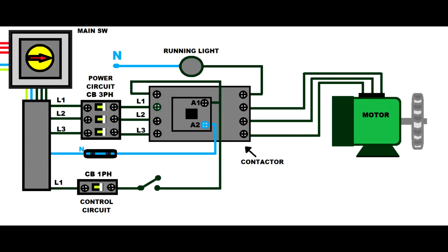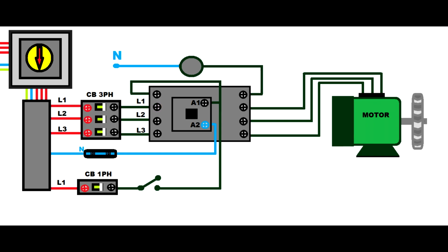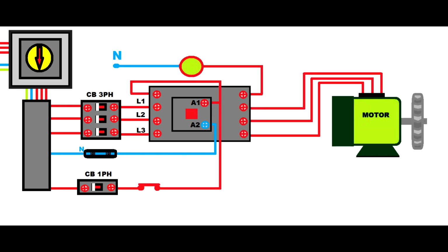Look at this picture. You'll observe you have the isolating switch, two circuit breakers, power and control, the contactor, and the motor. Let's see how this system works. We will turn on the isolating switch. The electricity will reach the power circuit breaker and the control circuit breaker. If we turn on the power circuit breaker, the electricity will reach the contactor. And if we turn on the control circuit breaker, the electricity will reach the switch. So now our system is on standby to run. So we'll energize the contactor and the motor will run.